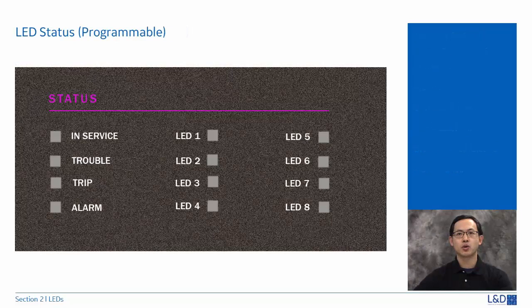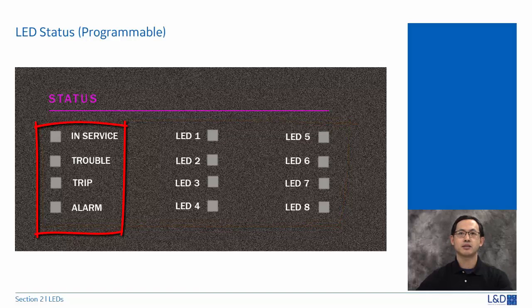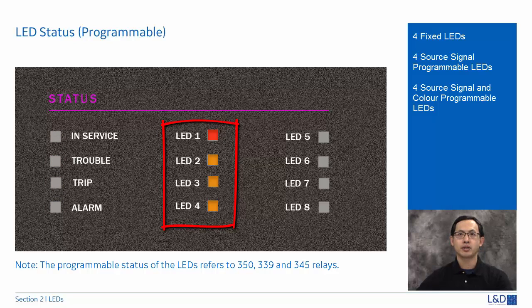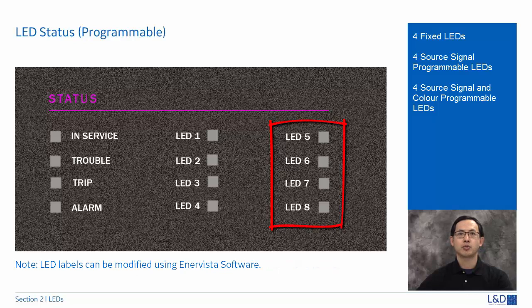The front panel with programmable LEDs has 12 LEDs. The first LEDs are dedicated to in-service, trouble, trip, and alarm, using the same color convention as non-programmable LEDs. The second group is for source signal programmable LEDs one to four: LED one is red, and two, three, four are orange. The third group is for LEDs five to eight, which are programmable in source signal and also in three colors: red, orange, and green.